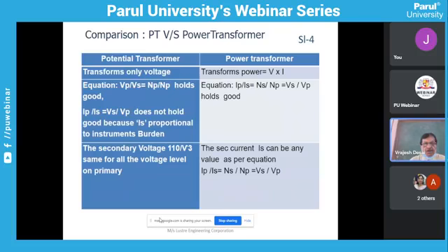So the equation Vp upon Vs is equal to Np upon Ns holds good here. Ip upon Is is equal to Vs upon Vp does not hold here, because Is is proportional to the instrument burden. We will study all this. What are the burdens which are connected to CVT? We call it burden and not a load, whereas that term is used for power transformer as a load, right? So here the equation is Ip upon Is is equal to Ns upon Np is equal to Vs upon Vp.